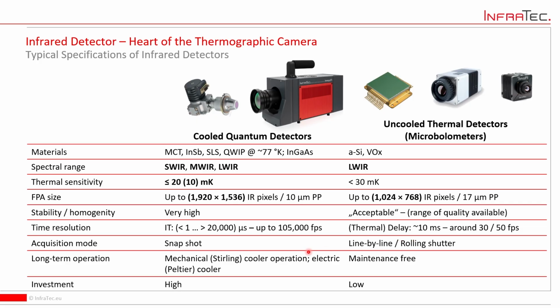The number two is these here have exposure times that can be controlled from very short to much longer, depending on the amount of radiation you're trying to capture. Only with infrared cameras, exposure time is called integration time. So this IT here stands for integration time. So that can go from the microsecond range up to the millisecond range.